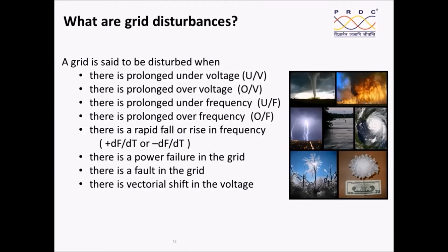Now, let us see what these grid disturbances are. The grid disturbances can be many. One is the prolonged under voltage in the system. As per the grid code, for example, for a 220 kV bus, the acceptable voltage limit is say 198 kV to 245 kV. When the voltage goes below 198 kV, say for example it stays at 190 kV for a long period, this is a prolonged under voltage. There is also prolonged over voltage. The acceptable voltage limit is 245 kV. If the grid voltage has become 250 kV for a long period, that is what we call prolonged over voltage.